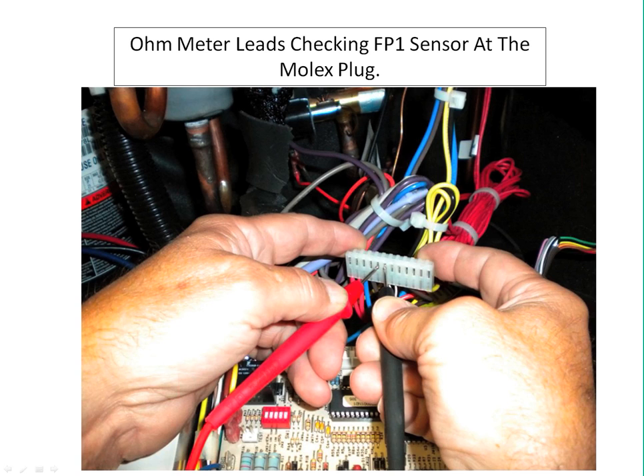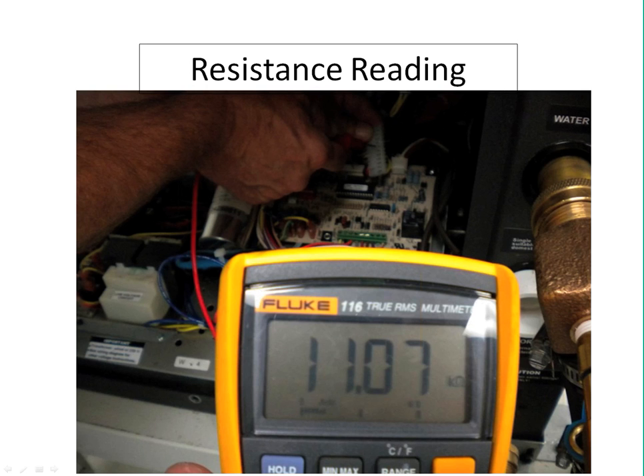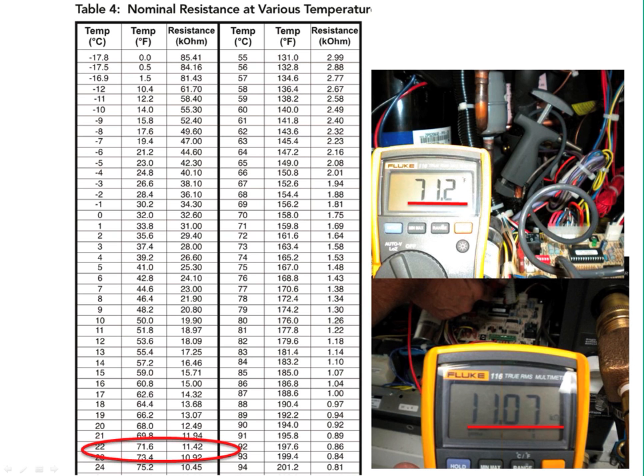So here's where I disconnected that Molex plug, turned it over and around so I can get access to it, making sure that I paired up the correct sensor leads, and I inserted the ends of my test leads onto those terminals with that corresponding thermistor. What I'm doing is I'm taking an ohms resistance reading, and in this example it showed it to be about 11.07 kilohms resistance. Remember, there is no voltage involved. This is all ohms resistance being measured and calculated.